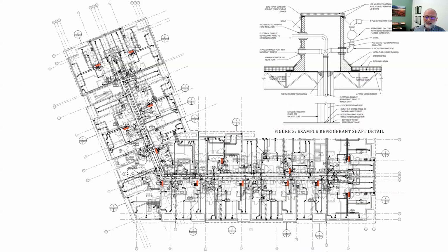However, additional complexity has recently been added to the use of split systems or VRF systems due to the new refrigerant change from R410A to R32 and R454B, which goes into effect next year. Because the new refrigerants are flammable, there are strict requirements related to running refrigerant piping through a building. This detail shows a shaft that's needed to run refrigerant piping vertically through a building. And the shafts need to have exhaust fans and refrigerant sensors. And you can see on the plan the number of shafts that would be required in this building.